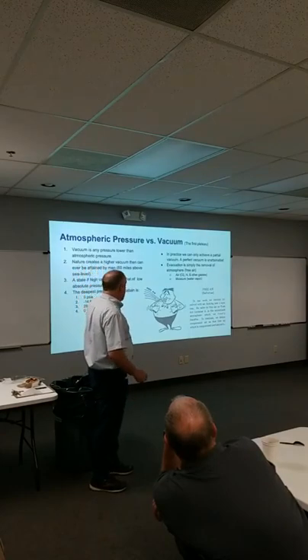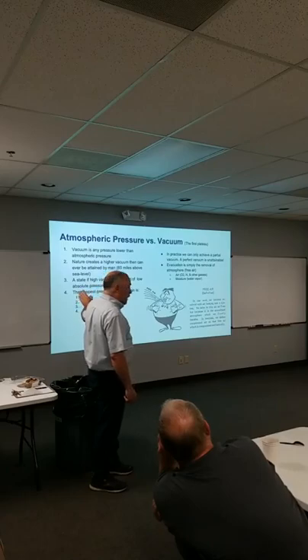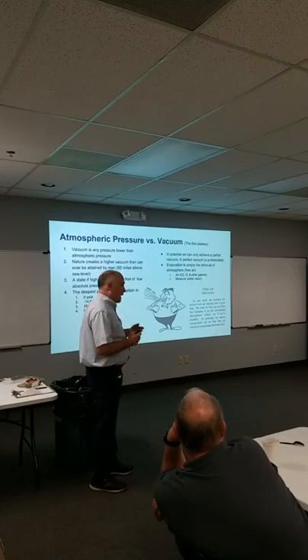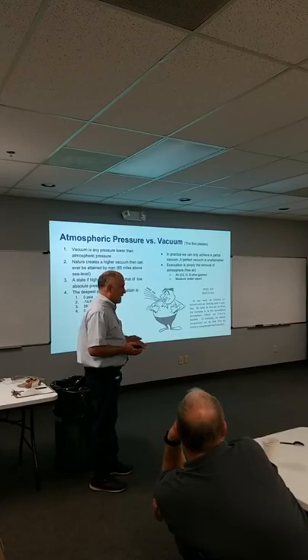Vacuum is just any pressure lower than atmospheric pressure. We said nature creates a higher vacuum than we can attain on Earth. A state of high vacuum is also a state of low absolute pressure. And here, the deepest vacuum was 0 psia, negative 14.696, 29 inches of mercury, 0 microns. But it's important to realize that on all the systems we work on, all we can achieve is a partial vacuum. And in our industry, when you say, I'm down to 100 microns, that's nothing.